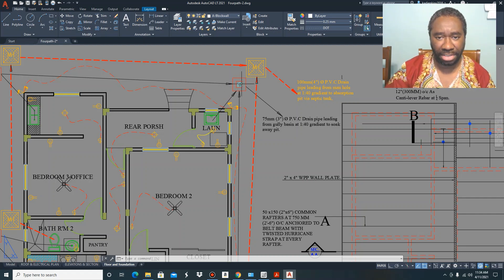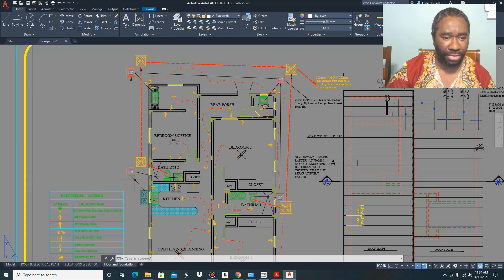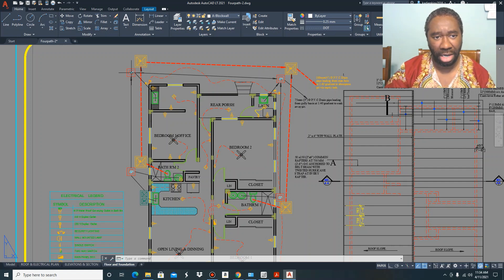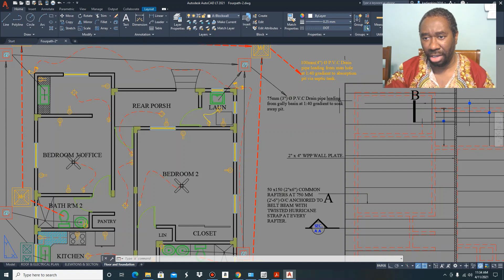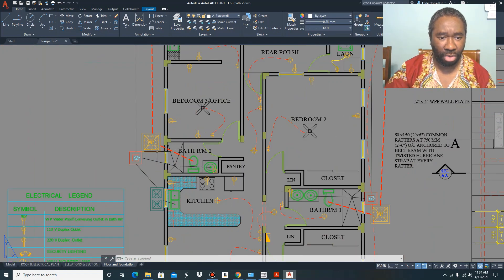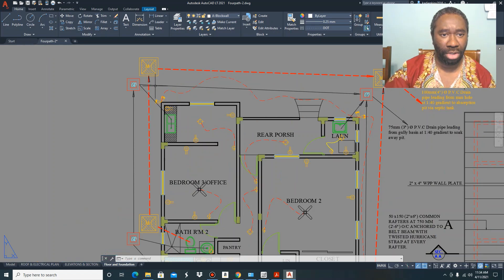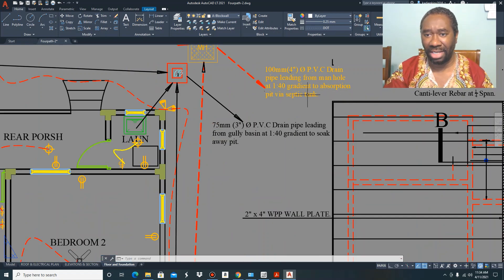As we move to the back of the building we can see there is a laundry, and the wastewater from that laundry is linked to the gully basin on the outside. On the outside, the wastewater that goes into your gully basin flows to another gully basin at a gradient of 1 in 40, then to another gully basin, and is eventually led to a soakaway pit. Similarly, the drainage water from your manhole links to another manhole and goes all the way through to a septic tank and then to the absorption pit.